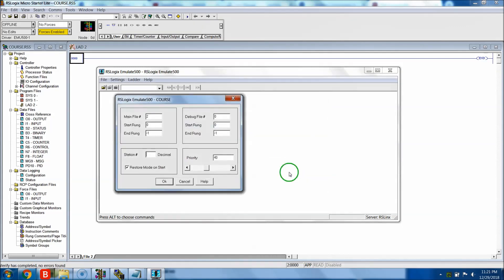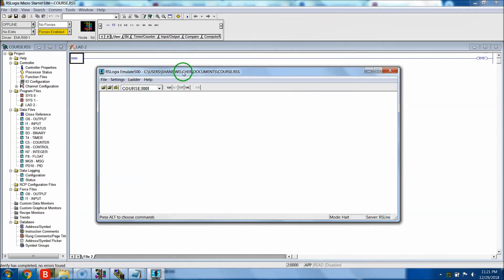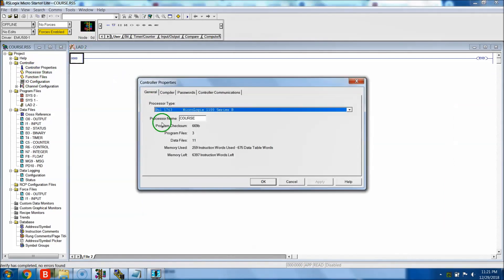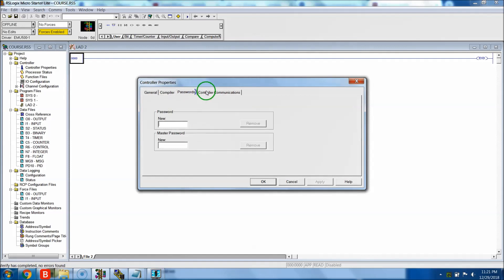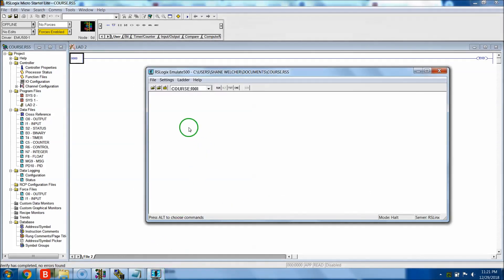At this point it's going to want to know the default settings. You know your station number from what you put in - we selected station zero, so hit OK. This now has the course file in it. I knew to use station zero because the node we selected earlier in the properties was zero - it says 'zero processor node' - so that's how I knew exactly what address to enter.